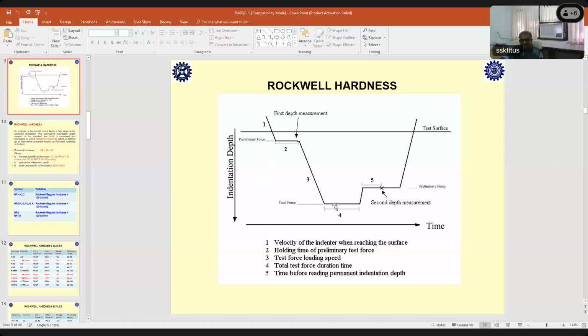Okay, so now what you have to keep in your mind very clearly is, in the Rockwell scale, we are using a conical indenter, which has an angle of 120 degrees and a curvature of 0.2 mm, and the velocity of the indenter reaching the surface has to be optimized. Holding time of the preliminary force has to be optimized as per the standard, and the testing force loading speed, this ram speed, is 1 to 4 seconds, as I said; this has to be optimized for a primary machine. And the total test force duration time has to be optimized. Then after that, you release the additional test force. Before reading the permanent indentation depth, there is a time given. Within that time you have to measure quickly.